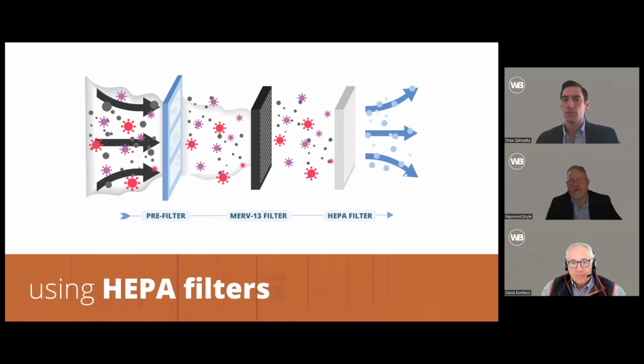In a lot of cases, Dave, you would consult a toxicologist or an EH&S or the safety person. Sometimes the user themselves that's in the lab may not have the expertise to know when it should be one or the other, whether it's 100% outside air or recirculated. So there are certain cases where you work with toxic or hazardous chemicals where they may want to consult an additional specialist to make sure that they are applying the right strategy to the airflow, recirculated or 100% outside air. Okay, thanks.